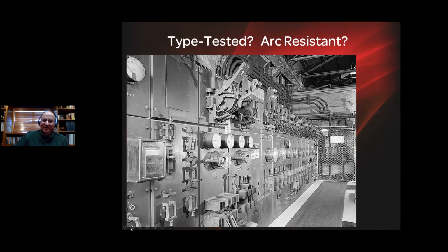So what about a really old Frankenstein era switchboard like this? Type tested, arc resistant? And the answer is, believe it or not, the switchboard was type tested in its day, very different standards back then. But the bottom line is, under internal short circuit events, it maintained enclosure integrity. None of those panels, which in this case you can see are bolted closed on both sides, will break open. But it's clearly not arc resistant because we have energized exposed assets on the front of the old style switchboard.